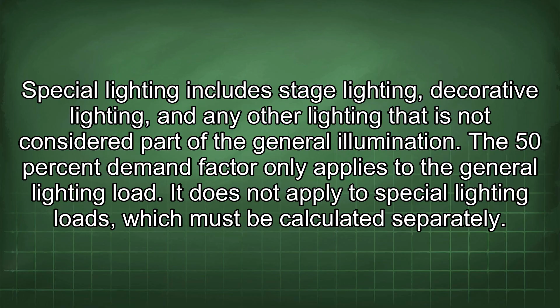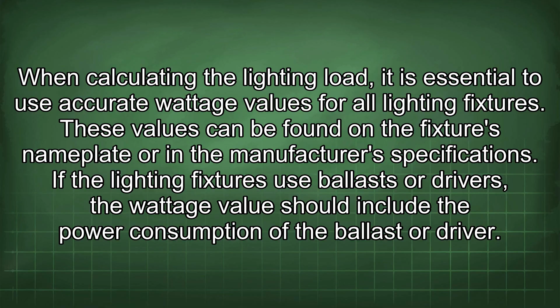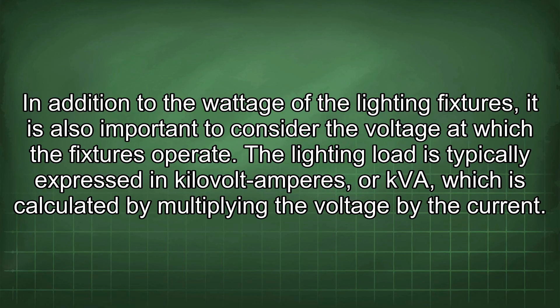When calculating the lighting load, it is essential to use accurate wattage values for all lighting fixtures. These values can be found on the fixture's nameplate or in the manufacturer's specifications. If the lighting fixtures use ballasts or drivers, the wattage value should include the power consumption of the ballast or driver. In addition to the wattage of the lighting fixtures, it is also important to consider the voltage at which the fixtures operate. The lighting load is typically expressed in kilovolt amperes, or kVA, which is calculated by multiplying the voltage by the current. If the voltage is not known, it can be assumed to be 120 volts for single-phase circuits or 208 volts for three-phase circuits.